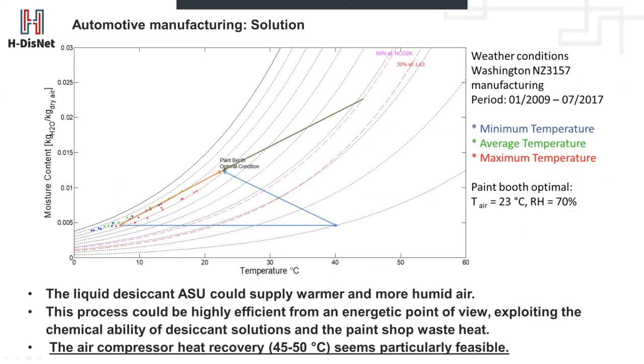We would use the source of heat from the heat recovery process from other parts of the paint shop to power that system. In summary, we found that across different times of the day we had different heating and cooling demands, but overall the technical viability of the system seemed viable. To achieve 23 degrees and 70% humidity, we costed up the system and worked out how much this retrofit solution would cost, and determined the return on investment. We found that's slightly under 3 years when you work out all the detail needed for this analysis. The savings are realized through using lower amounts of gas and electricity on site. That's my last slide.